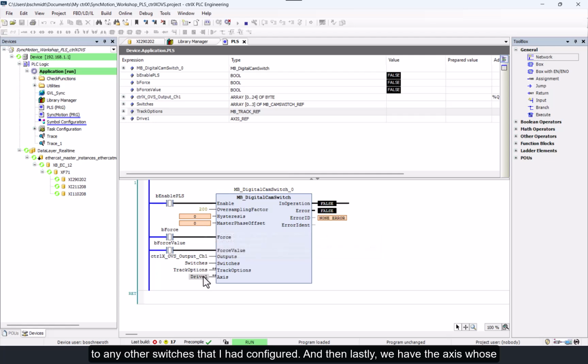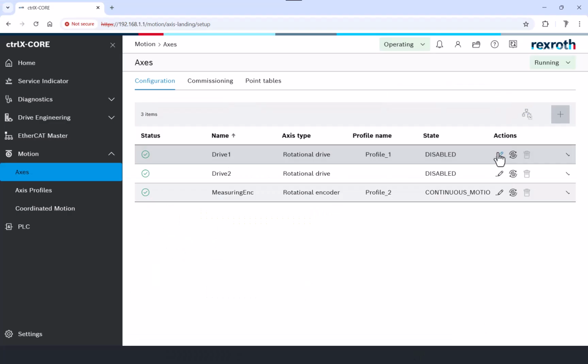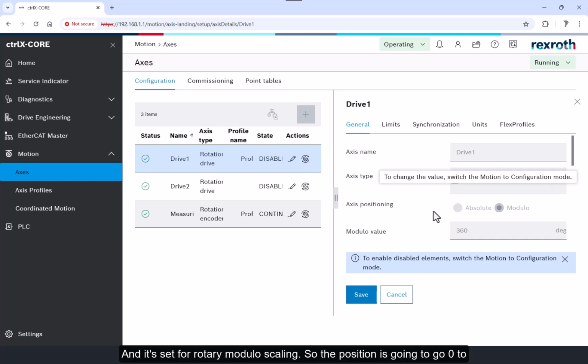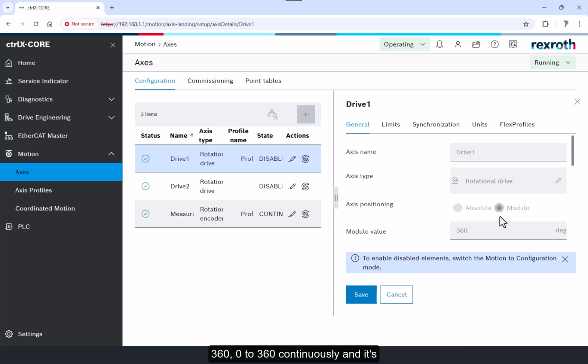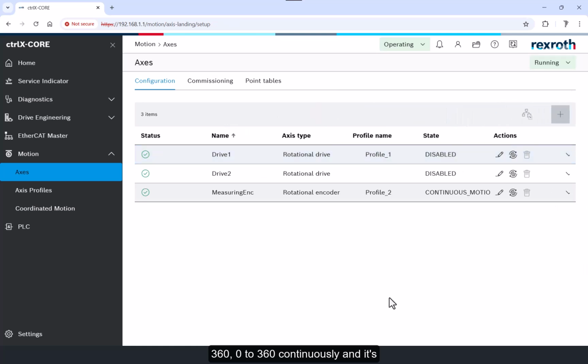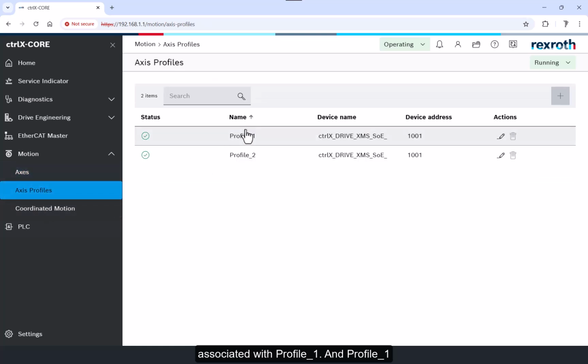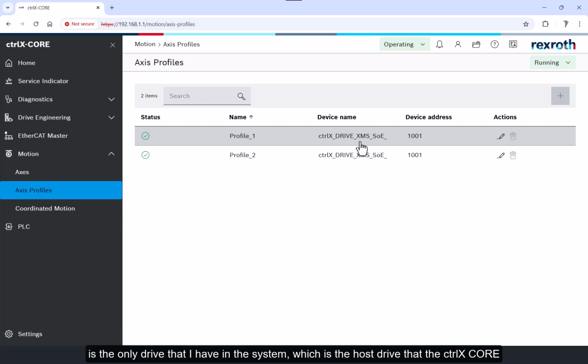And then lastly, we have the axis whose position is going to be used as the source for this PLS function. In this case, I have it configured for drive 1, which is a real axis. And it's set for rotary modulo scaling, so the position is going to go 0 to 360, 0 to 360 continuously. And it's associated with profile 1. And profile 1 is the only drive that I have in the system, which is the host drive that the ctrlX core resides in.